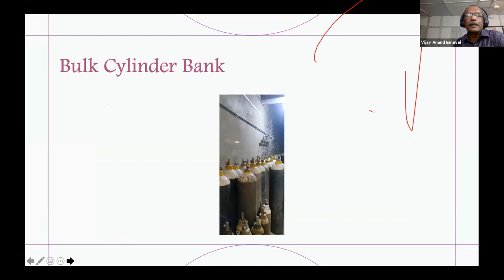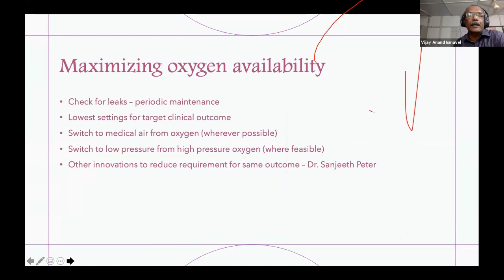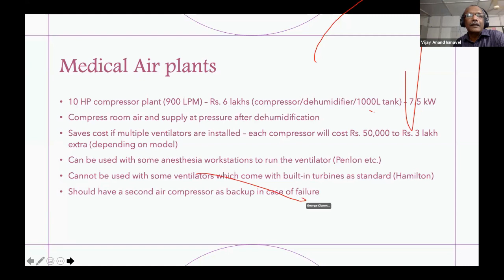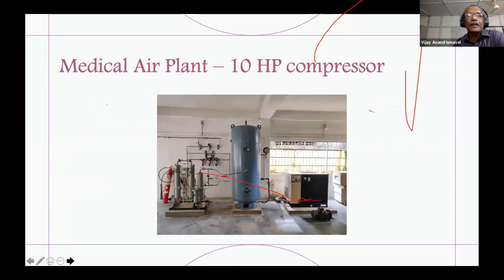To maximize oxygen availability, we have to keep checking for leaks, set the targets to the lowest settings, switch to medical air whenever possible, and switch to low pressure whenever possible. A medical air plant costs around 6 lakhs for a 10 horsepower plant, which gives about 900 liters per minute at 7.5 kilowatts. This is useful because it saves a lot of money, but you should check what type of load is connected to it. So that is our medical air plant, 10 horsepower.